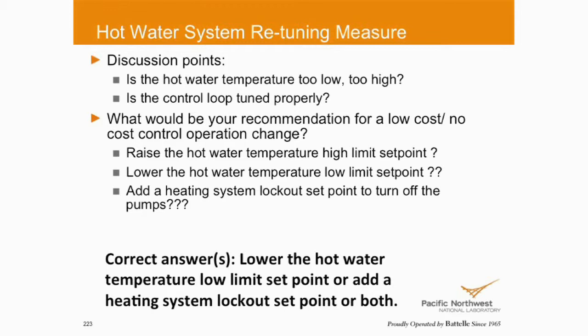Lower the temperature. Instead of resetting it down to 140, reset it down to 120, maybe even 100. We have some hot water loops that we run as low as 80 degrees. Now maybe that's too cold for what you guys are doing here if you're overcooling to dehumidify. But if it's steam fed through a heat exchanger.